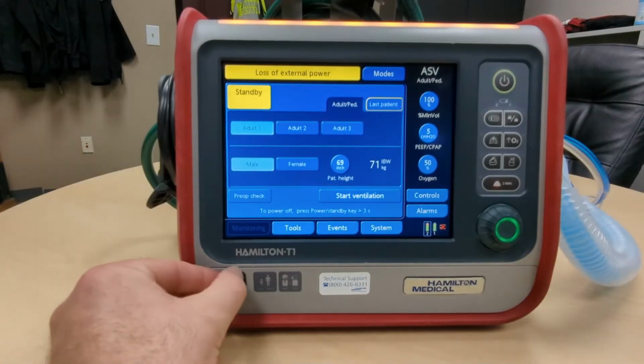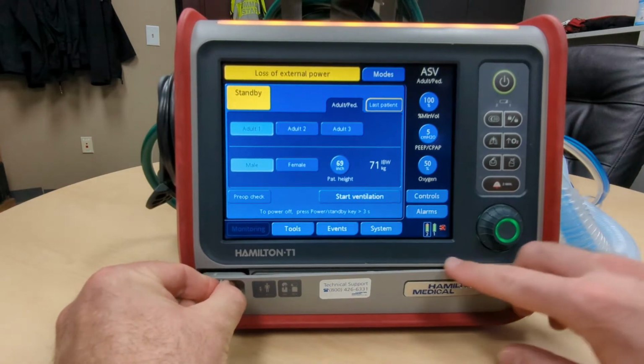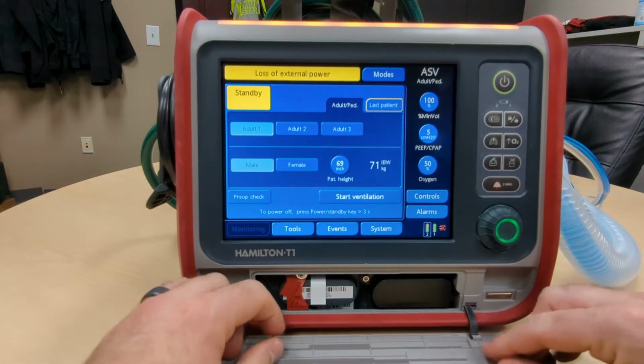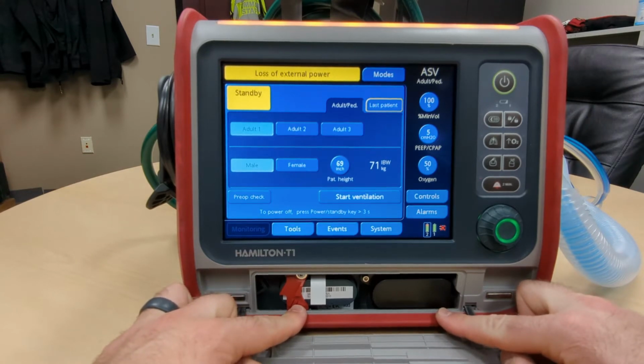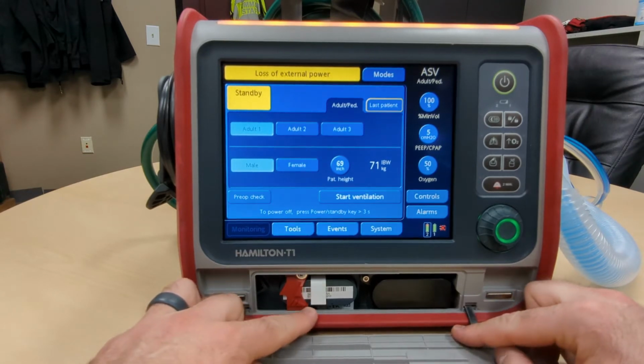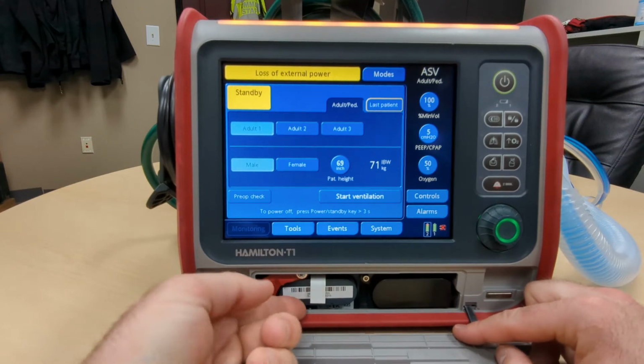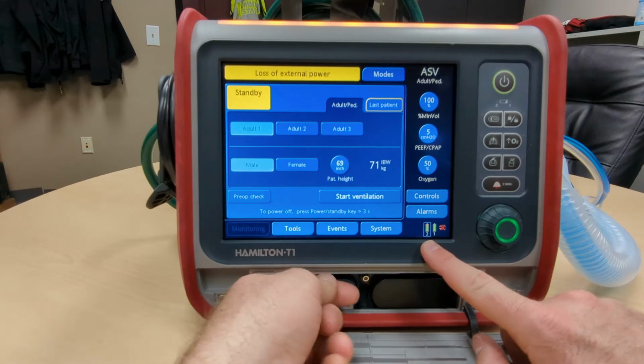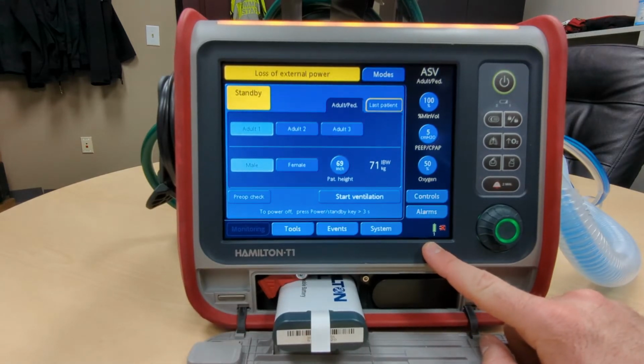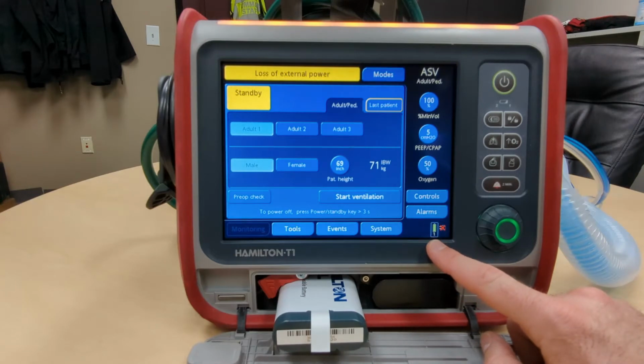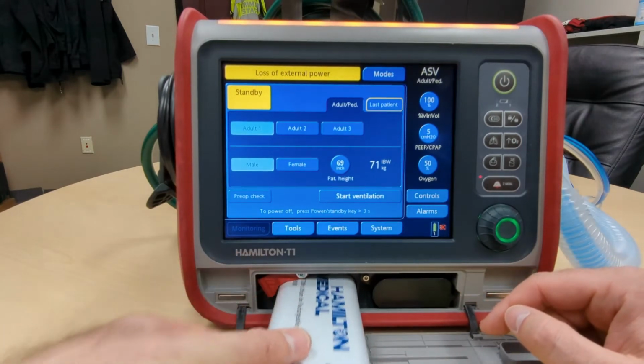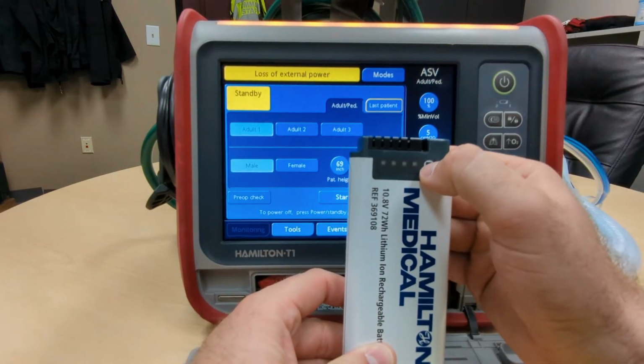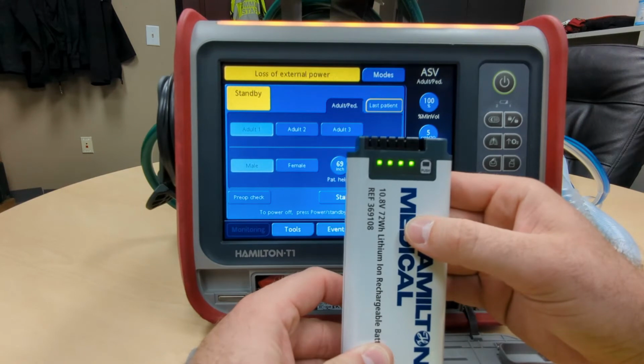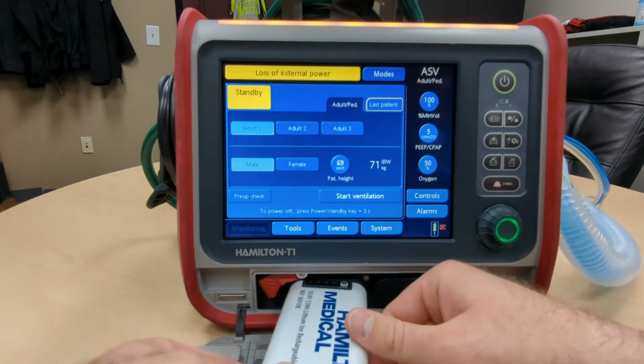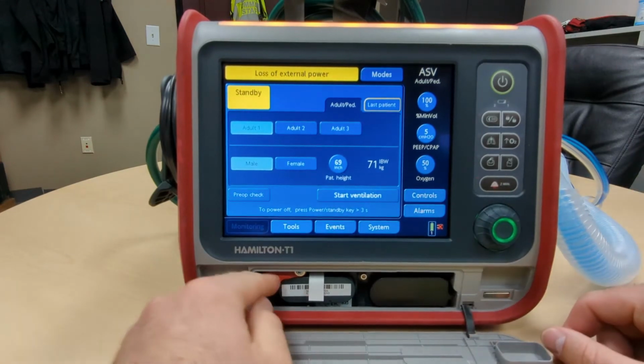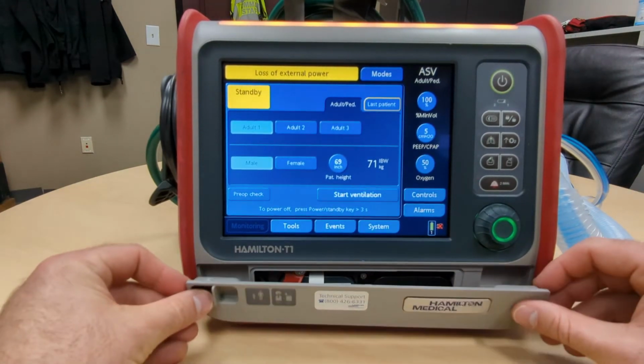Next, this is the battery door. It's magnetic, simply pull to release. We have 2 batteries in all of our Hamilton T1s. This is the fixed battery and this is the removable. If you flip this door, you're able to remove the battery, and you'll see here, battery 2 will go out. These are hot swappable, meaning that if the ventilator is on or off, if it's ventilating or not ventilating, you're able to swap the batteries. Additionally, the batteries have an indicator light for the amount of charge. Press in, door back down. Again, it's magnetic.